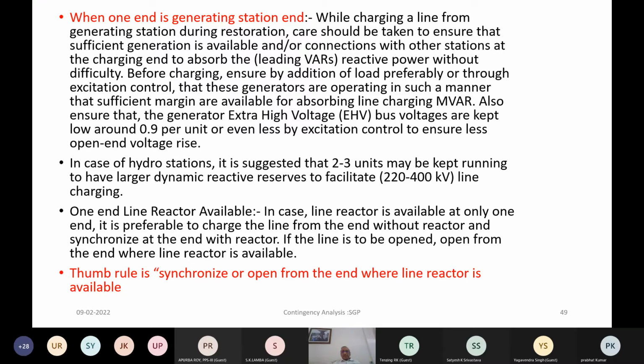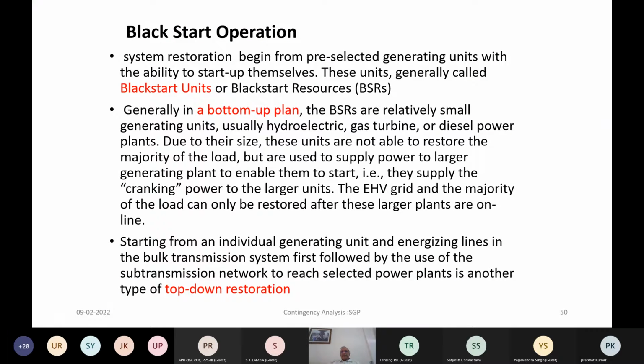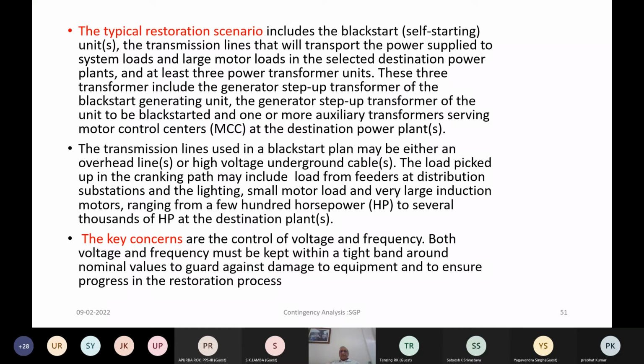The thumb rule is synchronize or open from the end where line reactor is available. So wherever line reactor is available, use of line reactor is recommended. And then the black start operation. Those hydropower stations where black start facility is available, they will be familiar with the black start operation. Typically, the key concerns are basically voltage and frequency control and controlling the line charging capability.